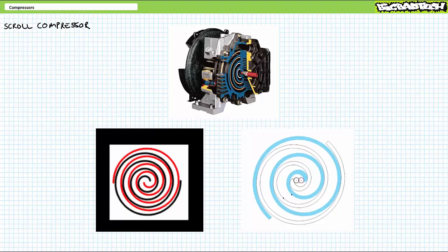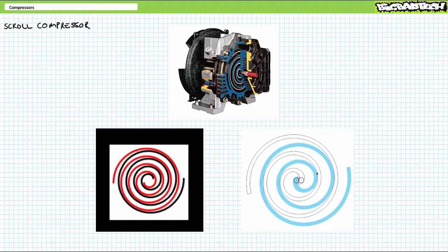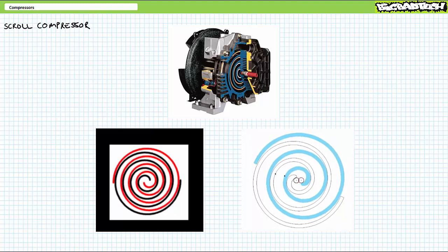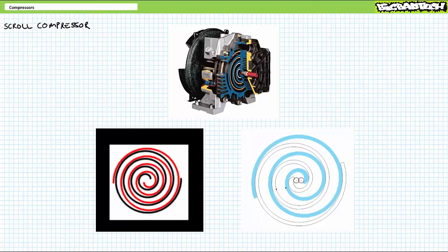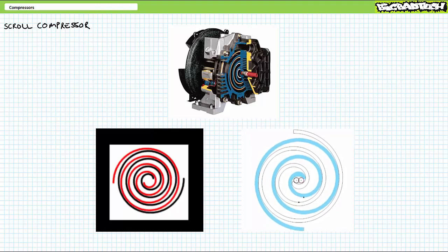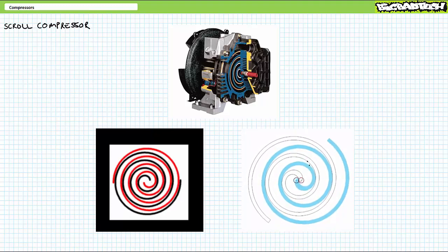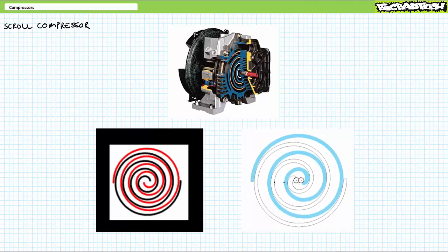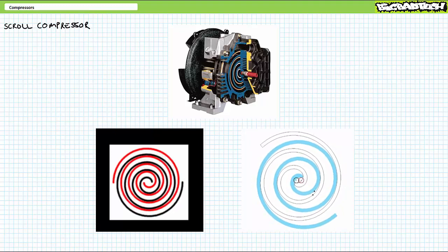Similarly, a scroll compressor is out of my artistic league, so I absconded with these publicly available images illustrating their operation. A scroll compressor uses two interleaving scrolls to compress air. Depending on design and how you look at it, a scroll compressor may or may not be considered a truly rotary device, such as some designs utilize a fixed scroll while the other orbits eccentrically without rotating, thereby trapping and compressing pockets of air between the scrolls. An entirely different design uses synchronized co-rotating scrolls, but with offset centers of rotation where the relative motion is the same as if one were orbiting. An apt analogy I once heard used to describe a scroll compressor is squeezing a tube of toothpaste, only the tube is not flat, it's a spiral. As interleaving scrolls inevitably draw together, they squeeze and compress the entrapped air and push it towards the outlet. If we were to extend this analogy to the previously discussed rotary screw compressor, one might envision performing the same squeezing action, only doing so in a helical fashion.